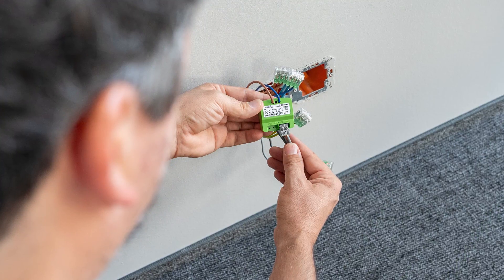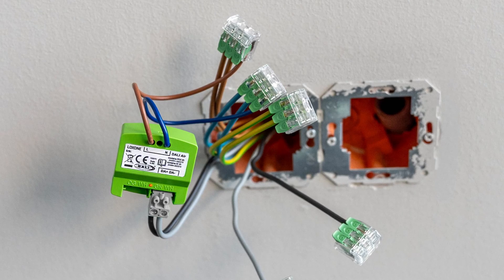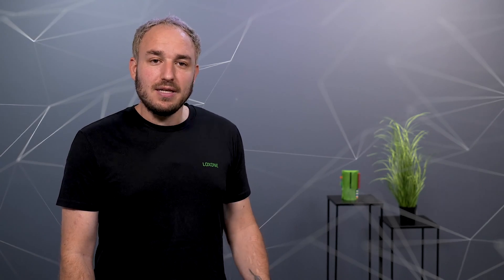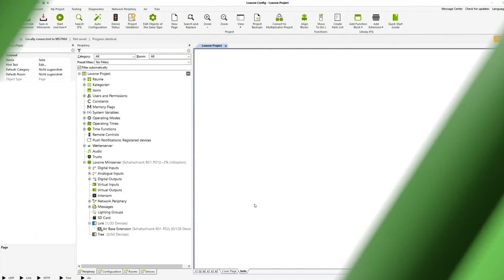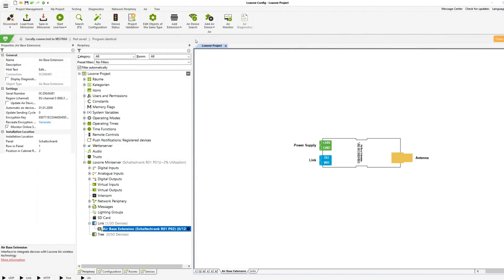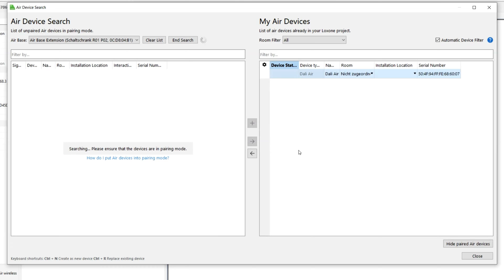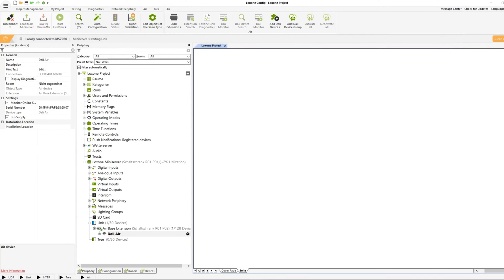Now let's look at the commissioning using the Loxone config. If the Dali Air is supplied with operating voltage 230V and is in the delivery state, the commissioning mode is automatically activated. This is signaled by the red-green-orange flashing LED on the device and it can now be found in the search dialog. If the LED flashes orange, the device has already been taught in once and no connection to the air base can be established. To reset the device to learning mode, you have to briefly interrupt the power supply. Once the Dali Air is found in the search dialog, you can identify the device by simply marking it — the LED on the device starts flashing quickly. Now you define the room and installation location, then save the configuration in the mini server.